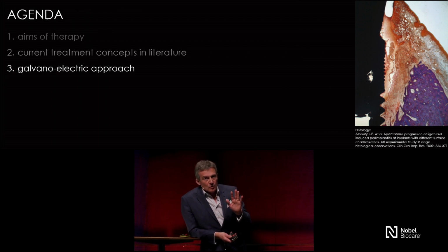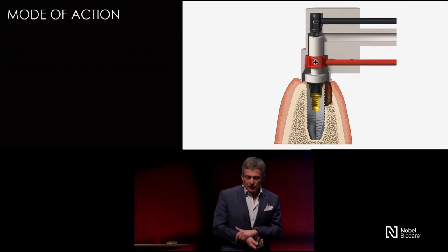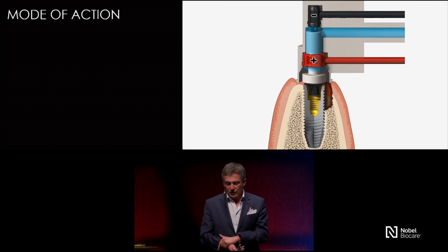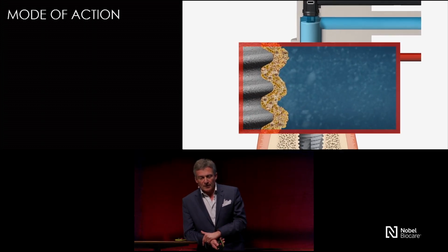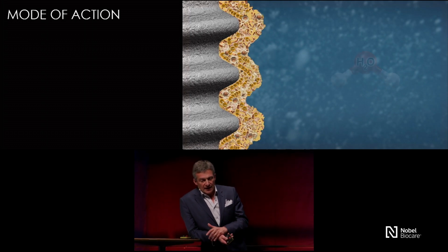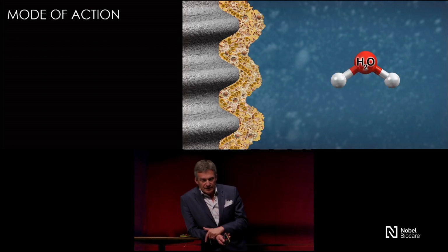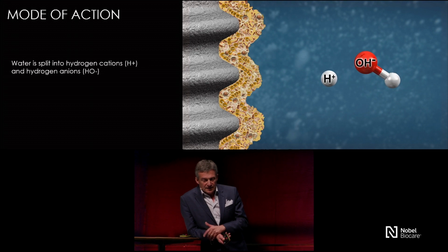If we load the implant with a current and we have ions, these ions would penetrate the biofilm within milliseconds and act on the surface. And I will show you how. In this image you see the connector and the spray head, and in blue you see the cleaning solution which allows the current. It has a conductivity which is appropriate.